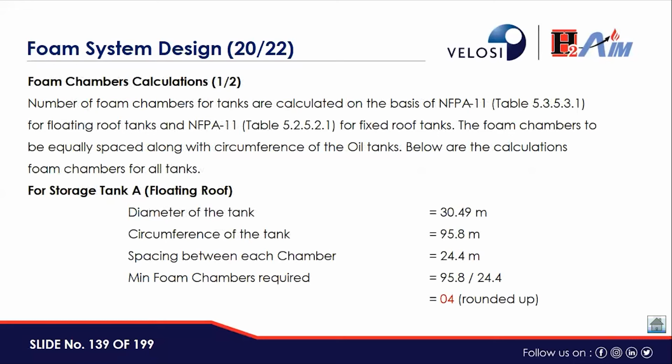So in foam system design, foam chamber calculations. The number of foam chambers for tanks is calculated on the basis of NFPA 11 for floating roof tanks and NFPA 11 for fixed roof tanks, with the foam chambers equally spaced along the circumference of the oil tanks. Below are the calculations of the foam chambers of all the tanks.